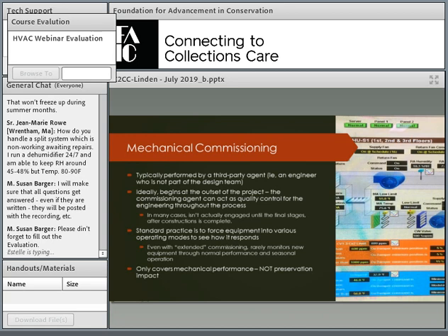It might be July, but they're going to force the system into a heating mode to see if it responds appropriately, whether the heating coil or humidifier kicks on, or whatever other operation might be. They're testing the system's capacity or capability, but rarely in the actual season, and rarely to see how the system will respond naturally. So the hiccup with mechanical commissioning is often that it's simply too short.